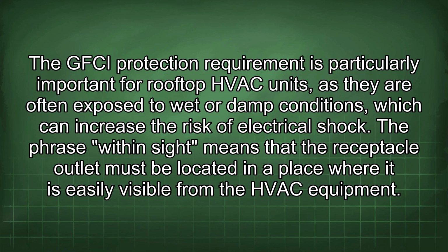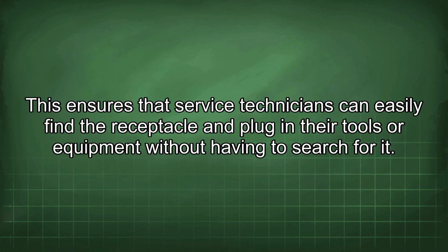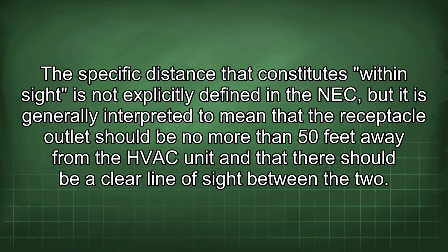The phrase within sight means that the receptacle outlet must be located in a place where it is easily visible from the HVAC equipment. This ensures that service technicians can easily find the receptacle and plug in their tools or equipment without having to search for it. The specific distance that constitutes within sight is not explicitly defined in the NEC, but it is generally interpreted to mean that the receptacle outlet should be no more than 50 feet away from the HVAC unit and that there should be a clear line of sight between the two.